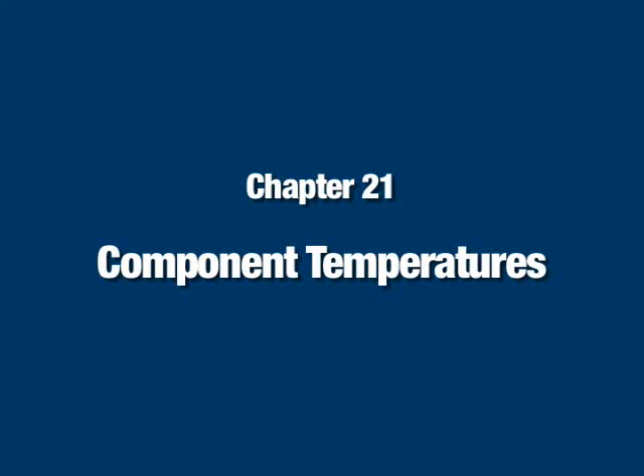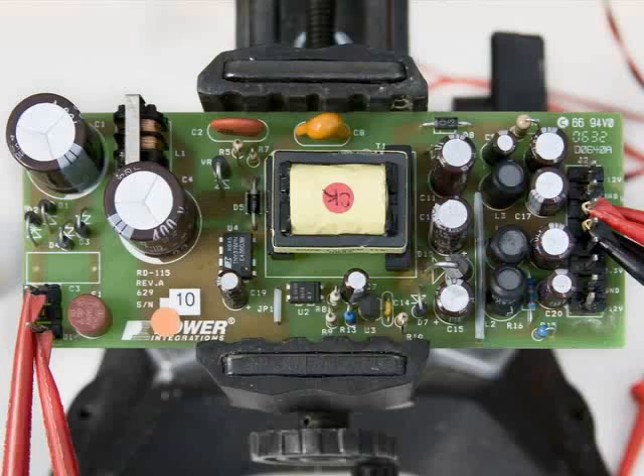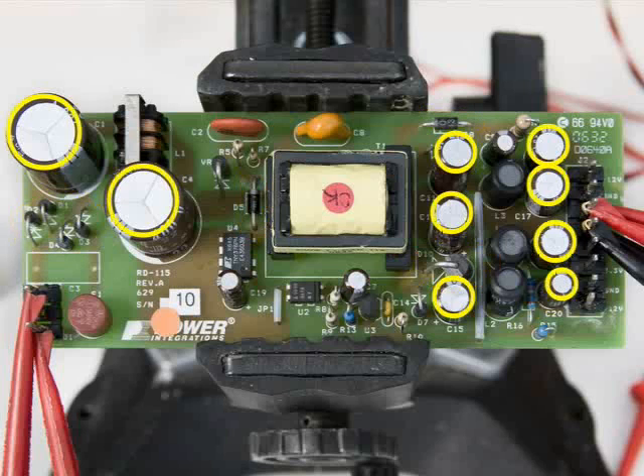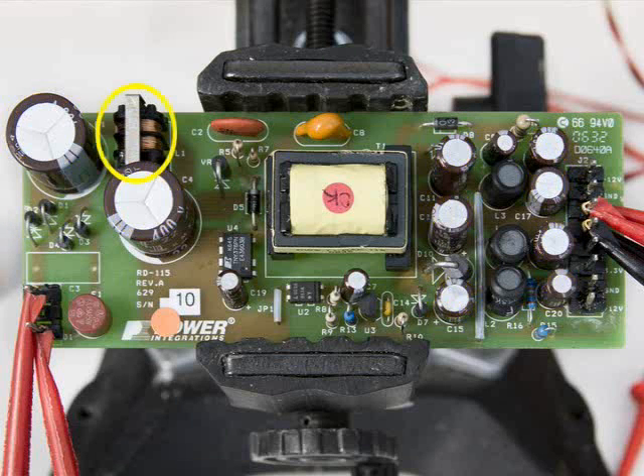Chapter 21. Component Temperatures. Measure the temperature of key components in your design, including diodes, electrolytic capacitors, common mode chokes, the transformer core, windings, and the Power Integrations device. These measurements should be performed while the supply is at full load and has been operating at room temperature for about 20 minutes. Take temperature measurements at both minimum and maximum AC input voltage. However, temperatures are usually highest at low line.